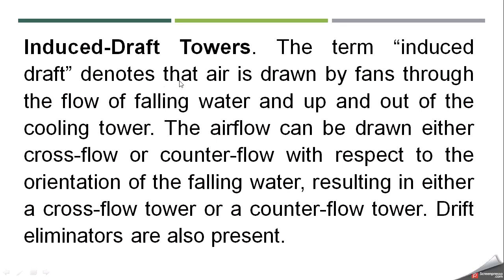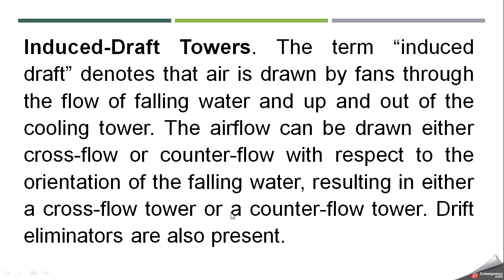In an induced draft tower, air is drawn by fans through the flowing water and up and out of the cooling tower. Fans are located at the top of the tower, sucking air upward. Airflow can be either cross flow or counter flow with respect to the falling water, resulting in water cooling. Drift eliminators are also installed. In these towers, air exit velocity is three to four times higher than entrance velocity, so recirculation is not a concern and separation of intake and outlet is not critical.